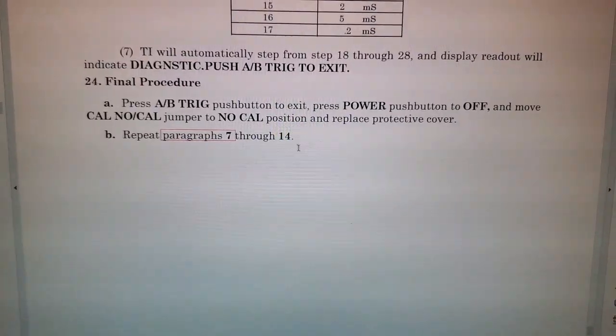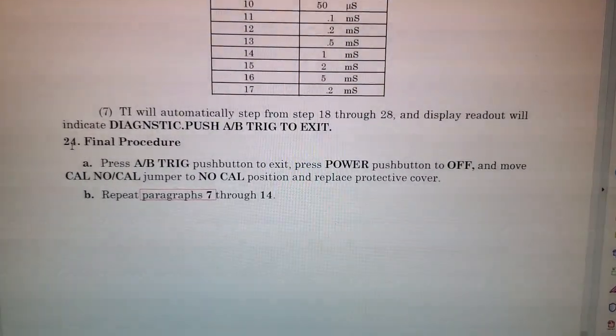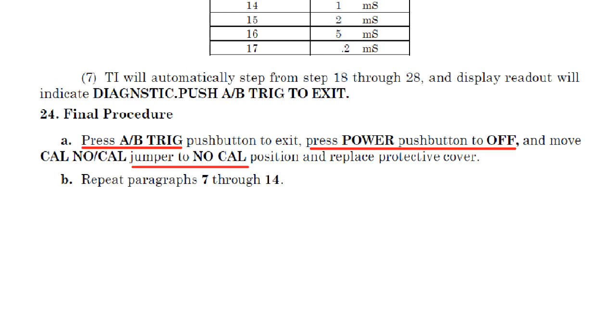Alright, here we are. It's on page 41 of the Army manual, and that's 24 alpha, which tells you to press the AB trigger, which gets you out of Cal diagnostics and back into regular scope operation. And then you have to turn the power off and then move the Cal, no Cal jumper into the no Cal position. If you don't do that, then you will lose your Cal stuff that you just did.